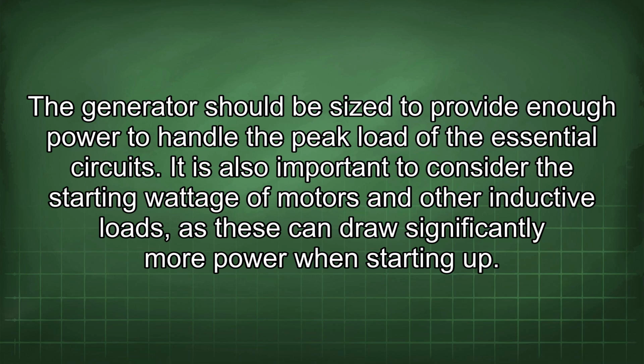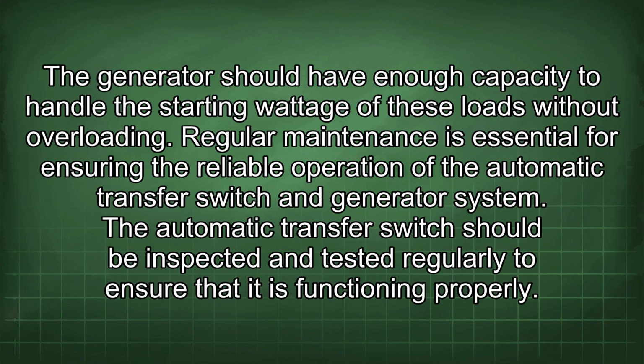The load calculation should take into account the wattage of all the lights, appliances, and equipment that will be powered by the generator. The generator should be sized to provide enough power to handle the peak load of the essential circuits. It is also important to consider the starting wattage of motors and other inductive loads, as these can draw significantly more power when starting up. The generator should have enough capacity to handle the starting wattage of these loads without overloading.